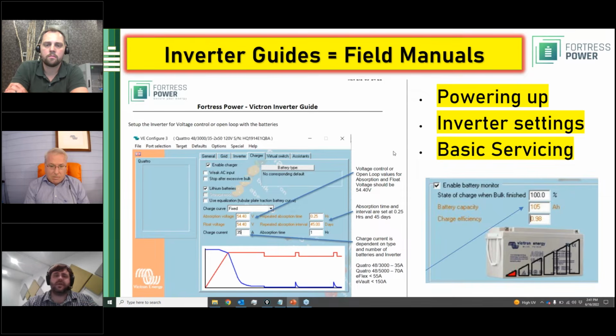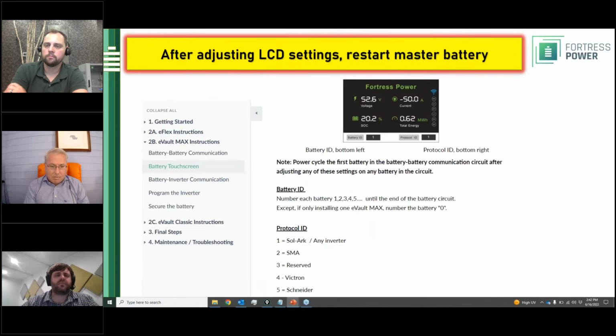So the field manuals or inverter guides cover powering up the system for the first time, programming the inverter settings, and also some basic service information, with more details found in the product manual of the individual battery. Our inverter guides contain instructions for both the eFlex and the eVault Max. The eVault Max requires you to program an inverter protocol ID, and Victron is number 4 on that protocol ID list, so that's information you'll need to know.